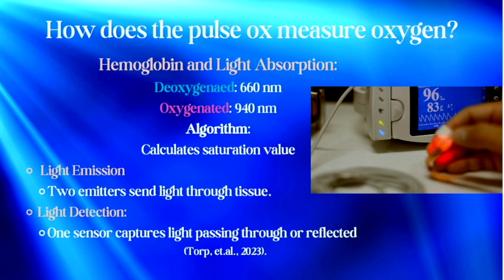The pulse oximeter probes have two light emitters and one light detector, or you can call it a sensor, and it's aligned to capture the light on the other side of the tissue bed, going through the skin, or the reflection of the light from a site such as your forehead.